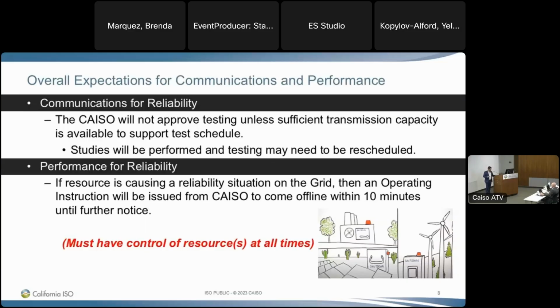Just one thing to add on ramping: it's easier to understand when you're receiving dispatches, like a 5-minute dispatch telling you to go from this to this. That seems to be getting dialed in. But during the testing phase, when you're not receiving dots, we see a lot of comments like, well, I told you I was going to 50 at the top of the hour. We can't just start up and go to 50. We expect Pmax minus Pmin divided by 5 minutes, even though you're not receiving 5-minute dispatches during the testing period. So whether you're receiving dots or not, we still want to see that ramp over a 5-minute period.